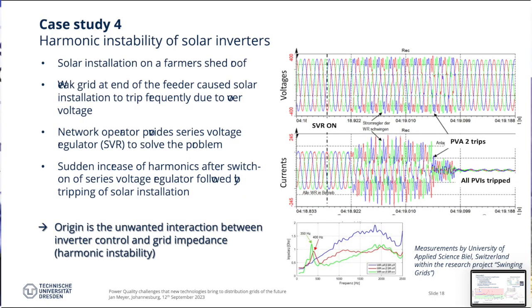Let's look at the next one, case study 4. That's in the harmonic range, and it's about instability of solar inverters. What is the basic condition? We have a farmer, and usually those farmers, also in Switzerland, have a large shed. And if I have a large shed, I can put a large PV installation on it. Often those sheds are a bit distant from the transformer station, which means you have a rather weak grid. So he installed his PV installation, connected it to the grid, and was really disappointed that he often tripped with overvoltage, which is fairly clear because of the high impedance of the network at the connection point.